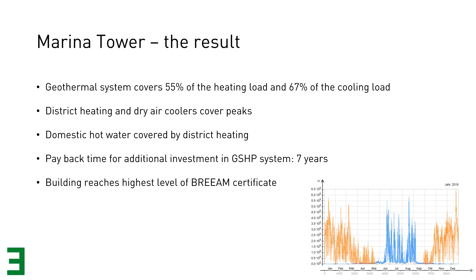There's a lesson learned from that construction site. Number one, and I think most important, something I stress to every new client: a dynamic building simulation of a more complex building is key to finding the commercial sweet spot of every ground source heat pump installation. Why? Simply because the size of the geothermal system can be pinpointed to the optimal commercial size if you know exactly what the loads of the building are per hour.